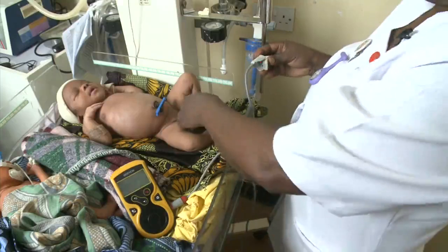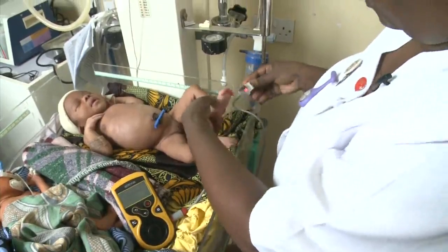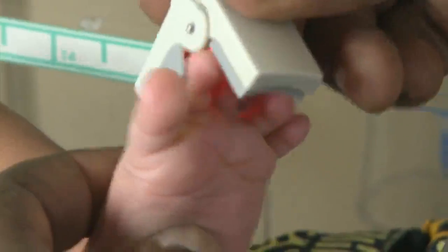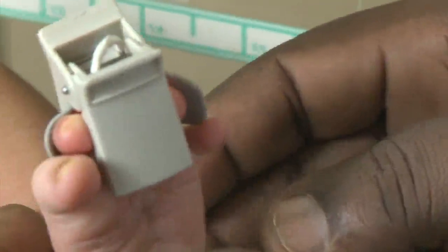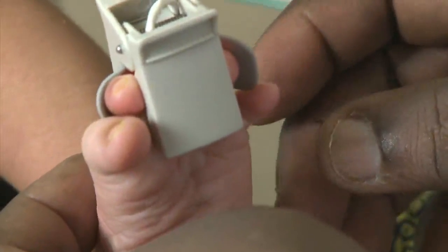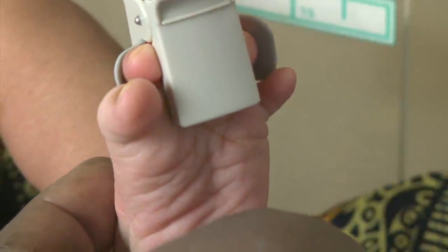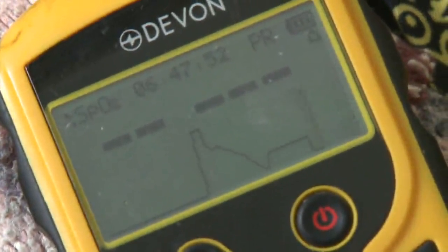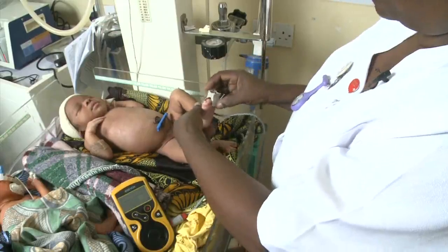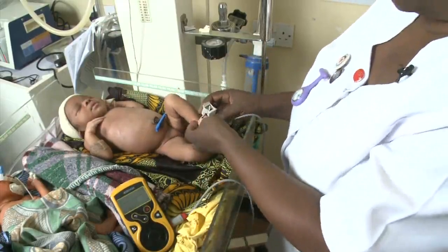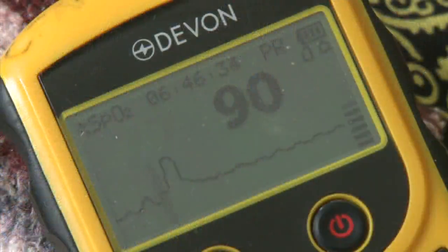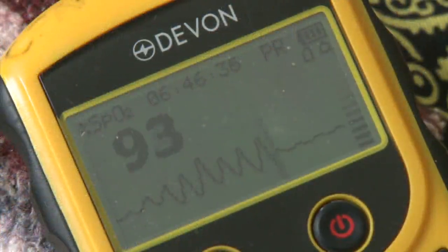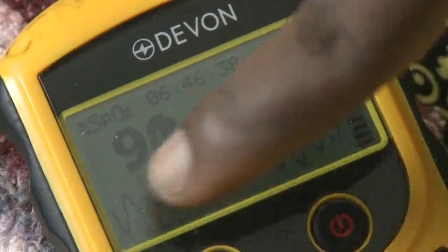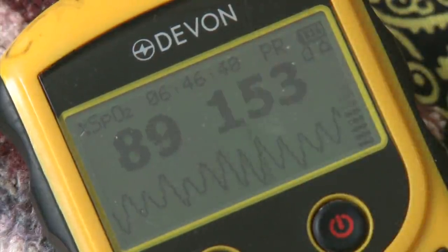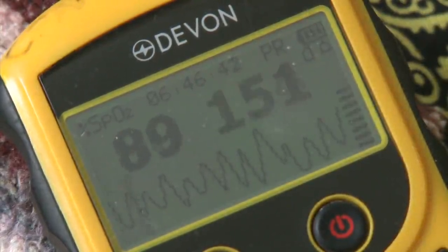A second criteria is to check the oxygen saturation. This is done with a pulse oximeter. To measure, put the probe on the fingers or toes of the baby. To get an accurate measurement, you may need to adjust these a few times until you get a continuous wave. It should be on one line. This is what a good waveform should look like.